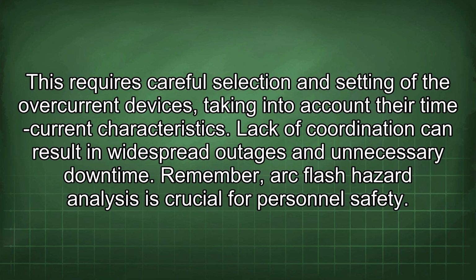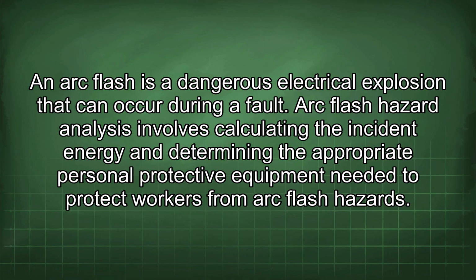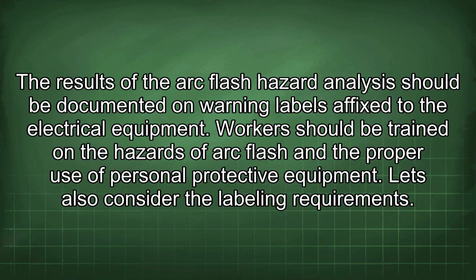Remember, arc flash hazard analysis is crucial for personnel safety. An arc flash is a dangerous electrical explosion that can occur during a fault. Arc flash hazard analysis involves calculating the incident energy and determining the appropriate personal protective equipment needed to protect workers from arc flash hazards. The results of the arc flash hazard analysis should be documented on warning labels affixed to the electrical equipment. Workers should be trained on the hazards of arc flash and the proper use of personal protective equipment. Let's also consider the labeling requirements.